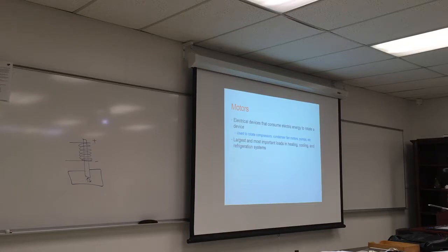It's called a squirrel cage fan. The squirrel cage fan basically provides some kind of pressure differential, and it will suck air from the room wherever it is and pump it out. And if you look here, this is the shaft where the motor is connected, and the shaft in this state is connected with a coupling. What is a coupling? Small piece of plastic that will extend the rotation part to another part.